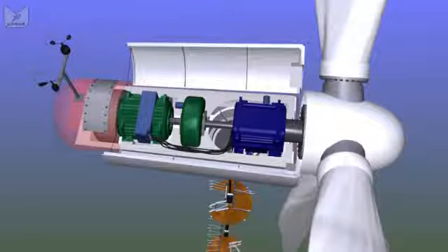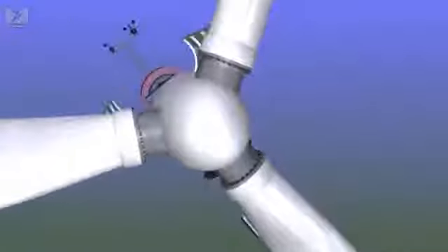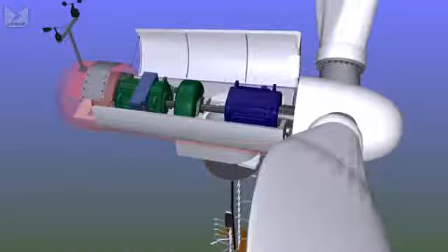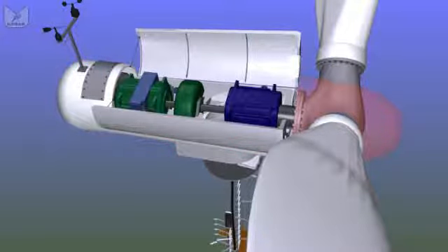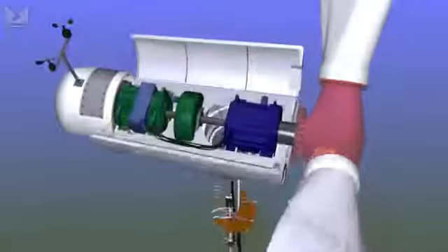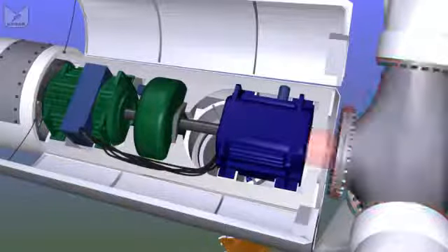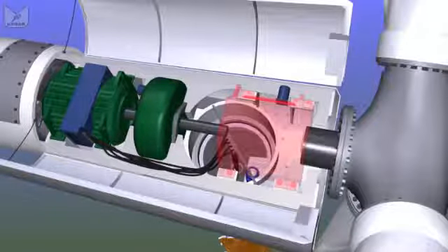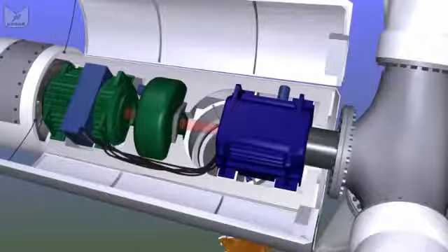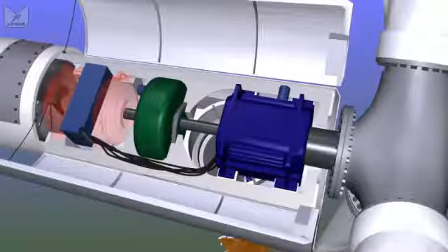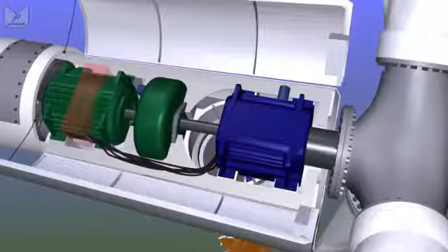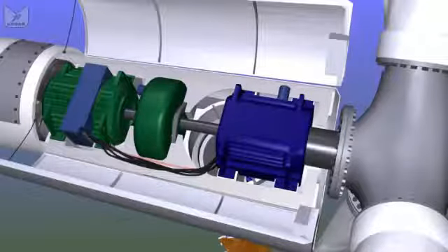The nacelle itself is just a fiberglass tube. At the front we have a similar fiberglass cowl protecting the hub, which is a steel casting on which we have bolted our three blades, and the blades can turn or pitch so that the angle they form with the wind can be varied. Out of the back of the hub we have a shaft which leads into the gearbox, then a high-speed shaft through a brake into a generator, and that generator then supplies the electrical power, as I say, at about 690 volts all the way back down the tower to the base.